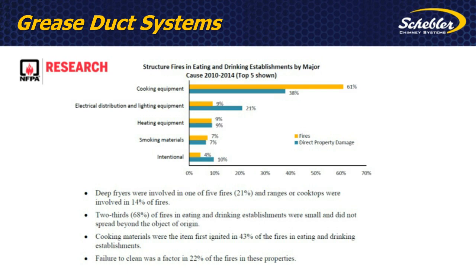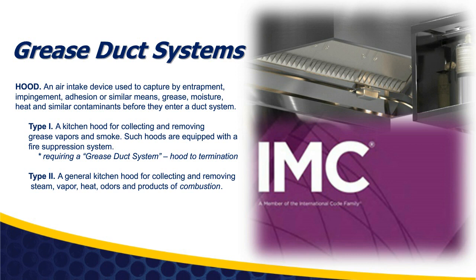Since today we're going to talk about grease duct systems, I want to use the International Mechanical Code to clarify what a grease duct system is and where it would be applied. There are 2 types of kitchen hoods for commercial kitchen operations. A type 1 hood is one that would collect and remove grease vapors and smoke from grilling operations or frying. Such hoods would be equipped with a fire suppression system. And because they are venting out grease vapors and smoke, they would be required to have a grease duct system from the connection to that hood with fire suppression to the termination of the system. Type 2 hoods would be for removing steam, vapor, heat, odors, and products of combustion, but they wouldn't carry grease-laden vapors, so they would not require a grease duct system attached to them.